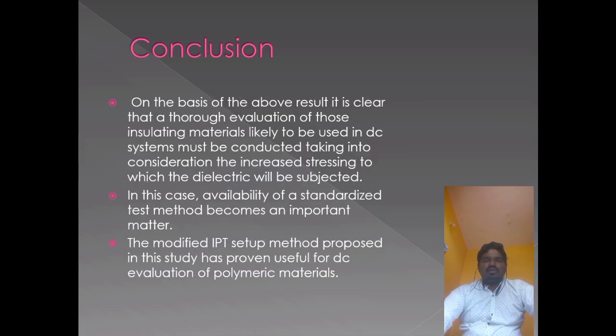Next will be the conclusion. On the basis of the above results, it is clear that the true evaluation of insulating materials likely to be used in DC systems must be conducted taking into consideration the increased stressing to which the dielectric will be subjected. In this case, the availability of standardized test methods becomes an important matter. The modified IPT test setup proposed in this study has proven useful for DC evaluation of polymeric insulation.